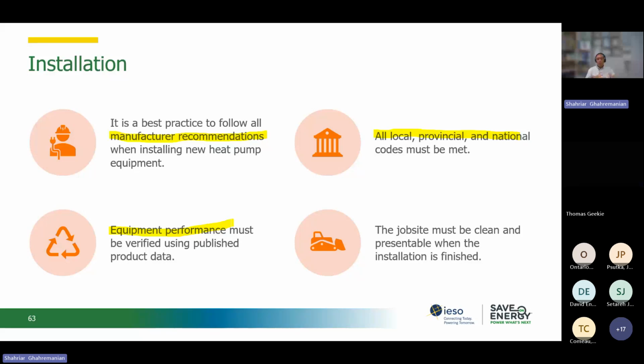And also the job site is really important. As I said, typically if we have a mechanical room, it's better that we install the outdoor unit, we call it an outdoor unit, inside the mechanical room, and then provide a good amount of airflow from outside. This will help with the defrosting of the air source heat pumps, and it also improves the efficiency of the system as well.